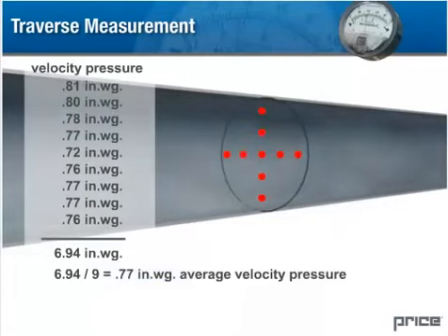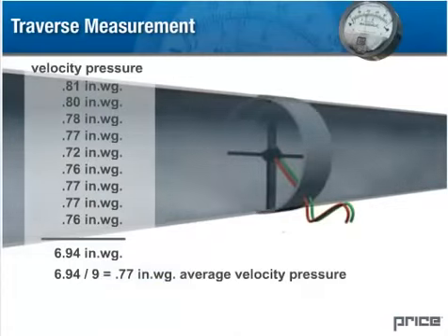In a functioning HVAC system, we would make use of the Price-SP series pressure sensor for measuring air pressure at terminal units. It is superior to the pitot tube in that it automatically receives representative pressure samples from across the cross-section of the duct and automatically averages them.